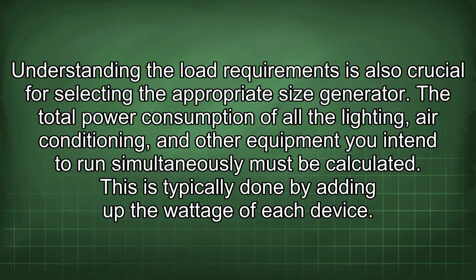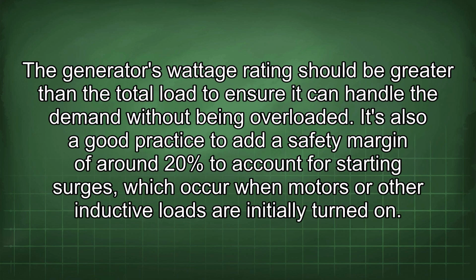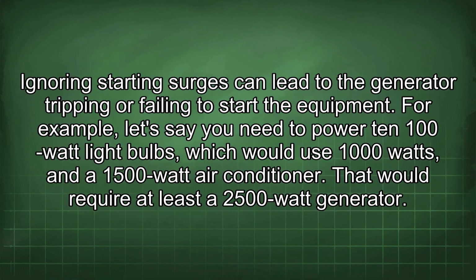The total power consumption of all the lighting, air conditioning, and other equipment you intend to run simultaneously must be calculated. This is typically done by adding up the wattage of each device. The generator's wattage rating should be greater than the total load to ensure it can handle the demand without being overloaded. It's also a good practice to add a safety margin of around 20% to account for starting surges, which occur when motors or other inductive loads are initially turned on. Ignoring starting surges can lead to the generator tripping or failing to start the equipment.